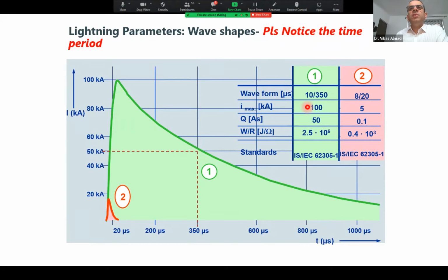So 10 microsecond is the rise time, and 350 microsecond is the time to half. That is why this wave is known as the 10 by 350 microsecond wave, because of the timing, not because of the current. Similarly, the red wave, which is the smaller one, rises in 8 microsecond and comes back to half in 20 microsecond. It is also seen that the amplitude of this wave cannot go very high. It is limited to a maximum of 20 kiloampere. And the green wave can go up to 200 to 250 kiloamperes.